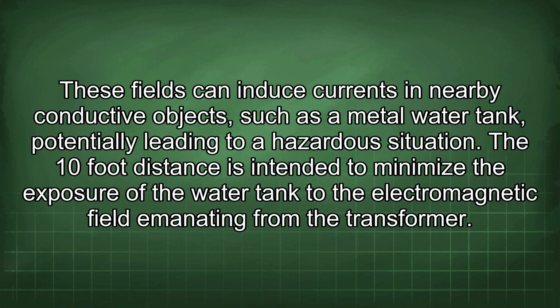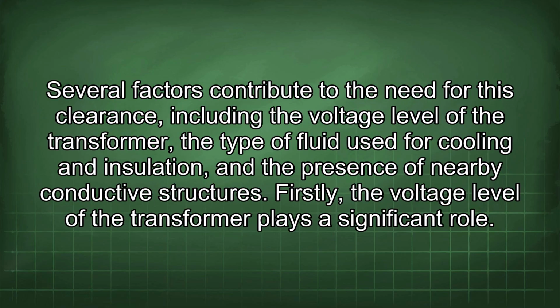These fields can induce currents in nearby conductive objects, such as a metal water tank, potentially leading to a hazardous situation. The 10-foot distance is intended to minimize the exposure of the water tank to the electromagnetic field emanating from the transformer. Several factors contribute to the need for this clearance, including the voltage level of the transformer, the type of fluid used for cooling and insulation, and the presence of nearby conductive structures.